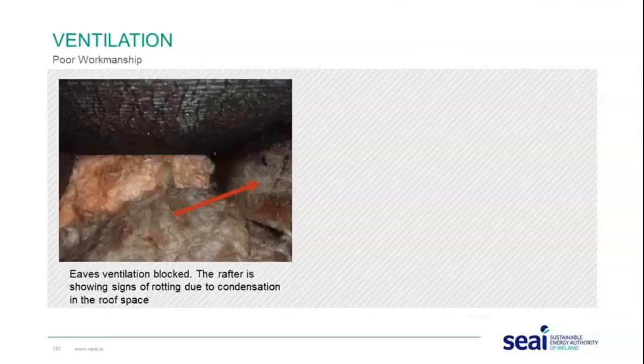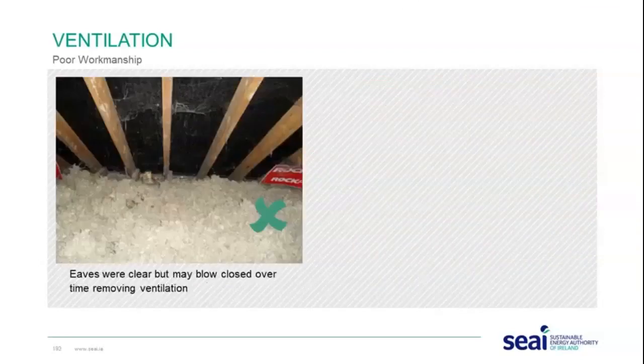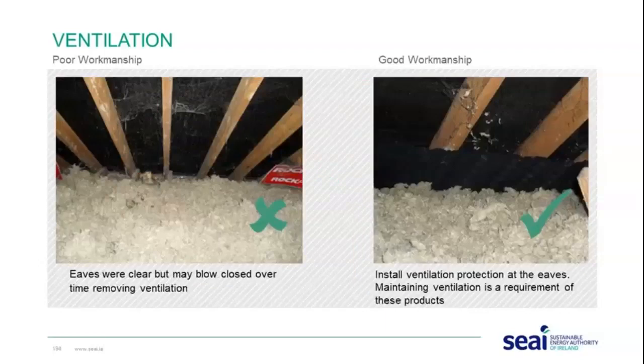Poor ventilation workmanship examples include eaves ventilation that is blocked, with the rafter showing signs of rotting due to condensation in the roof space — it is very important to maintain ventilation at the eaves. Another example shows saturation of insulation transferred through the plasterboard ceiling causing mould growth and health issues for occupants. Eaves that were left clear may blow closed over time, removing ventilation — installing protection at the eaves to maintain ventilation is therefore good practice.